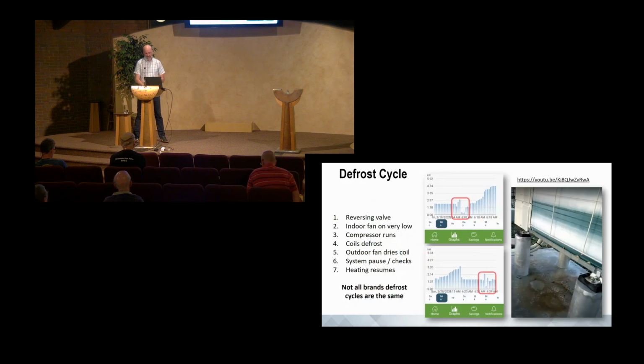Going back to the defrost cycles: this little ramp up in the power, this little peak, is ramping the fans up to high speed. It doesn't show up much on the power side, but you'll get about 1 to 3 minutes, maybe 90 seconds, of higher fan noise once an hour or so. That's what mine does. If you're really cold, really snowy, and in a shady spot, you might see it every 45 minutes or so, but it depends. It sounds like a refrigerator outside most of the time.